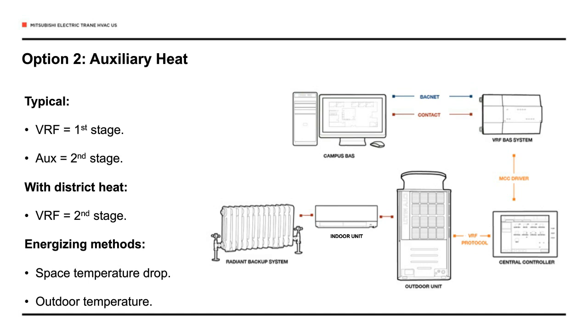We're going to talk about two methods for energizing auxiliary heat. Auxiliary heat can be either electric or hot water or gas, really any source of heat. It can be duct coils mounted downstream of a ducted air handler, either electric or hot water. It could be baseboard electric wall fin radiation or baseboard hydronic wall fin radiation. So this takes on a number of different ways what the auxiliary heat can look like in a building.